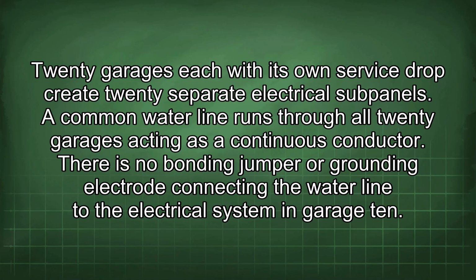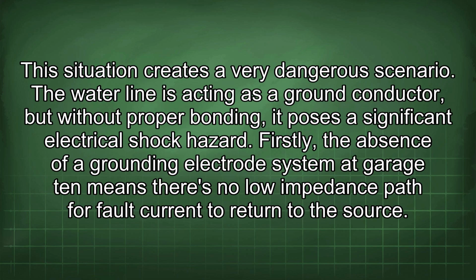20 garages each with its own service drop create 20 separate electrical subpanels. A common water line runs through all 20 garages, acting as a continuous conductor. There is no bonding jumper or grounding electrode connecting the water line to the electrical system in garage 10. This situation creates a very dangerous scenario. The water line is acting as a ground conductor, but without proper bonding, it poses a significant electrical shock hazard.